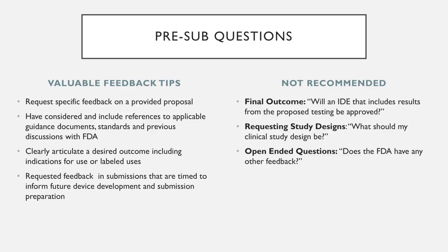And lastly, open-ended questions such as, does the FDA have any other feedback, is likely not going to be met with any kind of success. The whole purpose of the pre-sub process is to get guided feedback on specific questions that the medical device company wants. The FDA doesn't have an inherent interest in the medical device company or their success, so they're not going to have any other feedback based on this. They are there to help, but it's up to the company to request specific feedback.